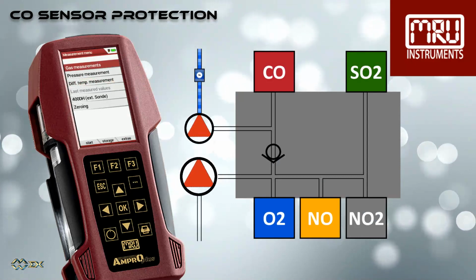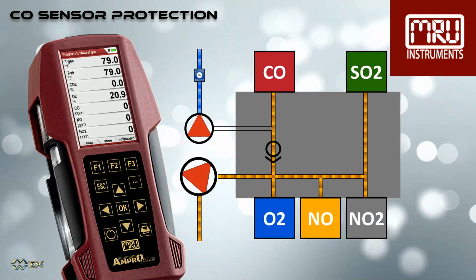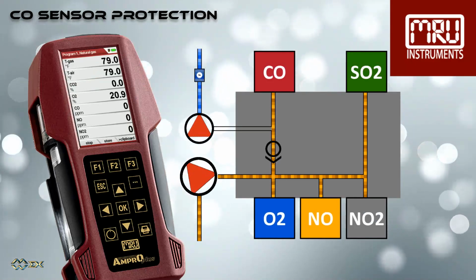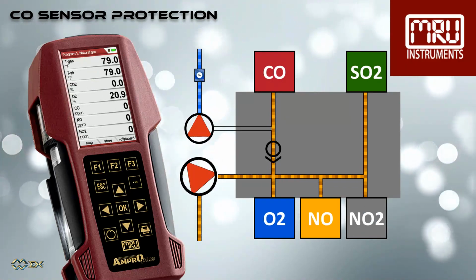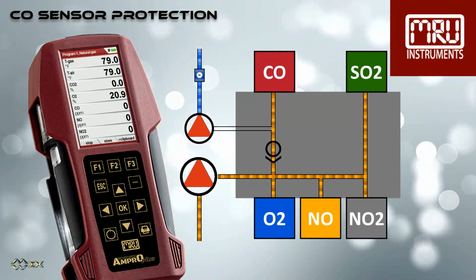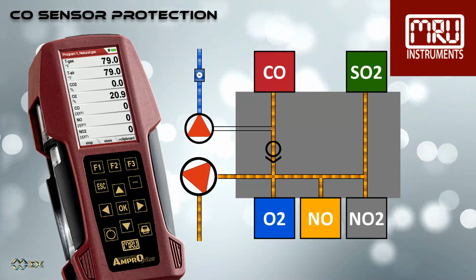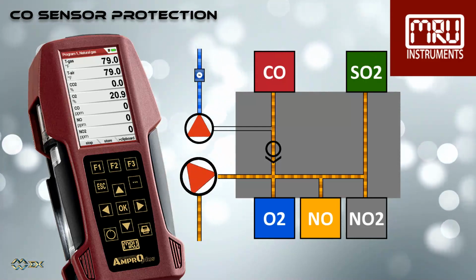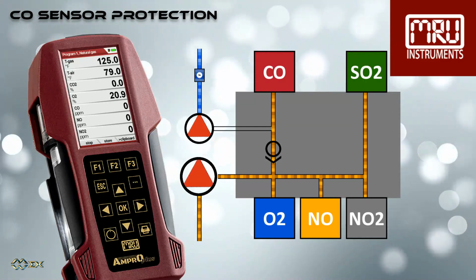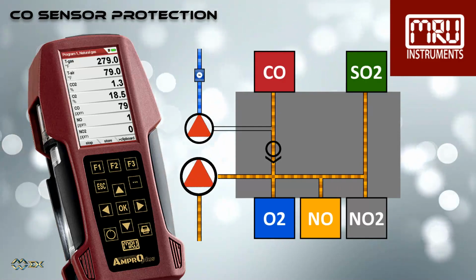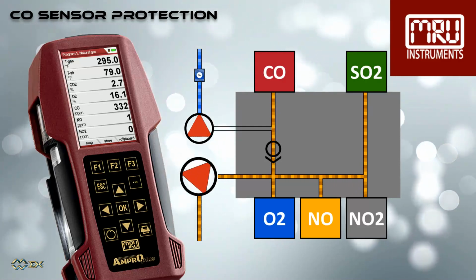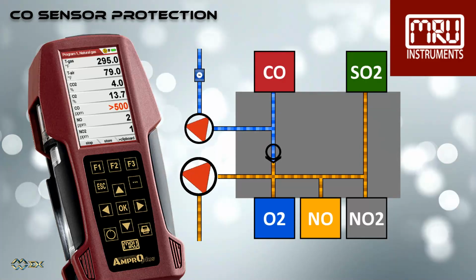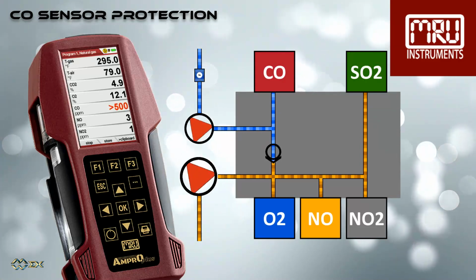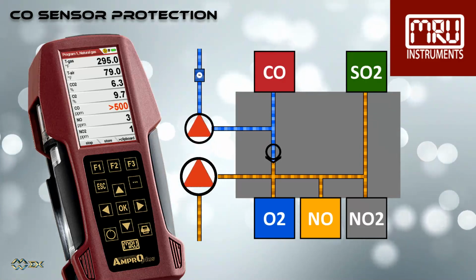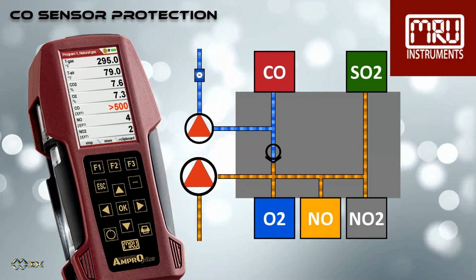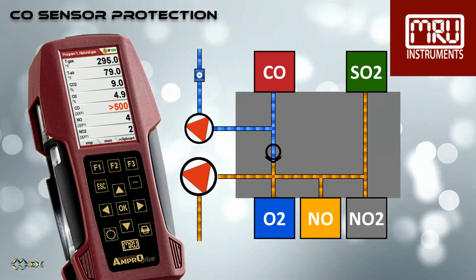Let's say you are inserting the probe into the stack and there is a concentration of 8,000 ppm of CO. The analyzer will extract this gas using the gas pump and then pump the gas to the individual sensors. The CO sensor will soon read CO values that are higher than the CO threshold and will then immediately activate a secondary air pump which will dilute the extracted gas and prevent additional gas from entering into the CO channel. This function will also be displayed on the analyzer display, showing that the CO threshold has been reached and that the CO protection pump is active.